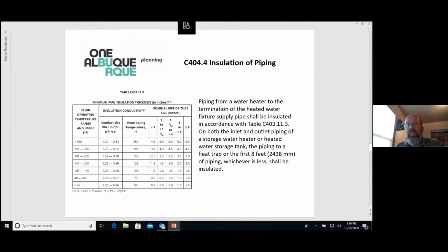And again, the insulation of the piping, there's the chart again. And now we're talking about domestic. Again, the thickness and the insulation factor for all the piping. The hotter the piping, the thicker the insulation, which I would imagine in the 105 to 140 category, which is where domestic hot water is.